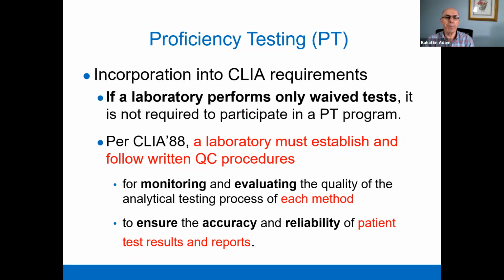Okay, now, if a laboratory performs only waived tests, it is not required to participate in proficiency testing. Okay, per CLIA 88, a laboratory must establish and follow written QC procedure, quality control procedure.